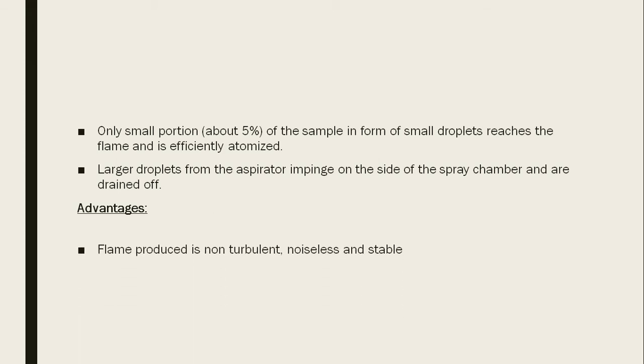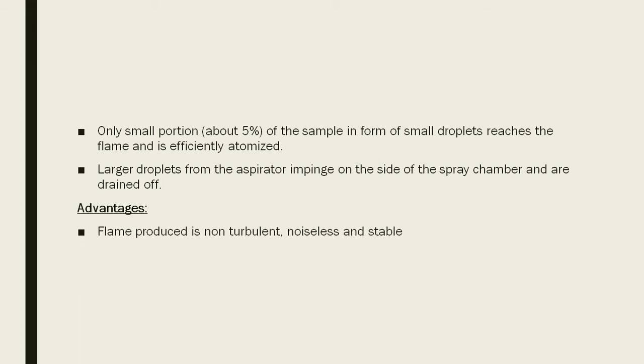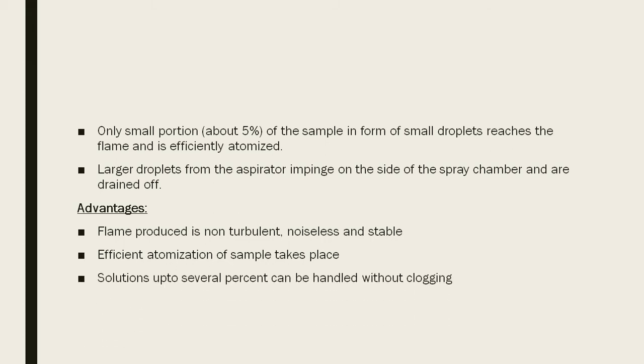The advantages are that the flame produced is non-turbulent, noiseless as well as stable. Efficient atomization of the sample takes place because the sample has a long path length to reach the flame, and also it is mixed properly before actually reaching the flame. Solutions with up to several percent solids can be handled without clogging. Since only small droplets reach the flame, there are no chances of clogging due to larger droplets.